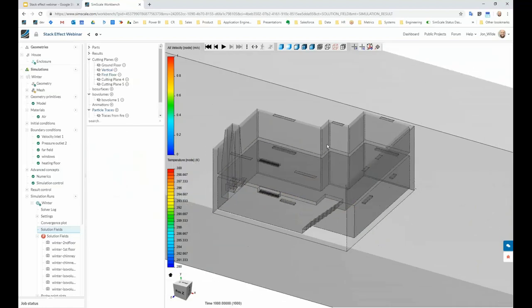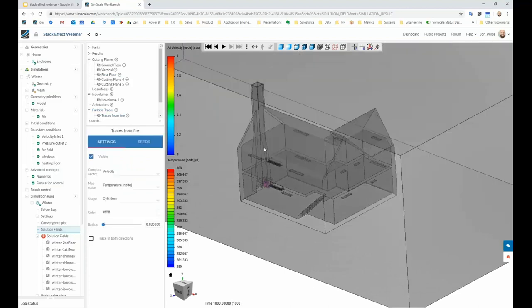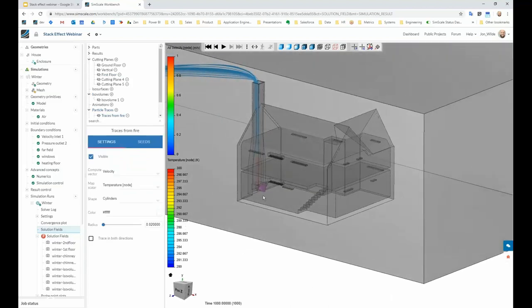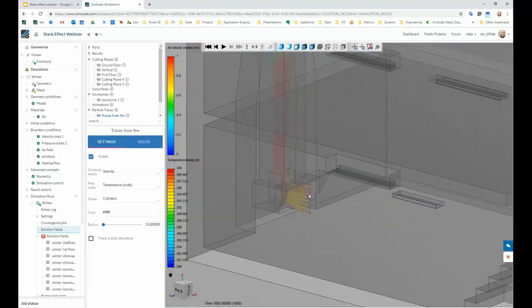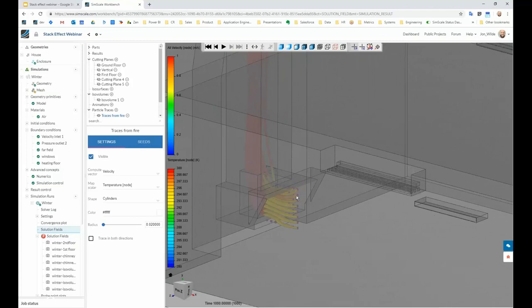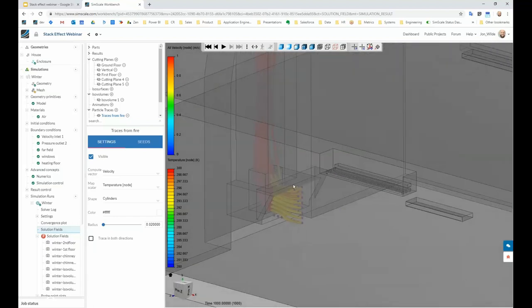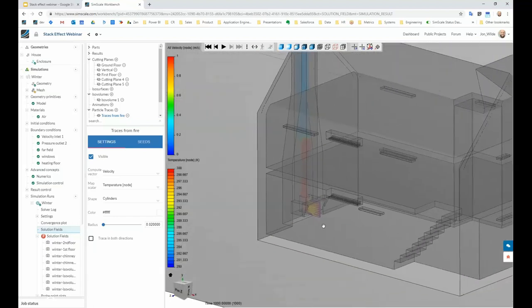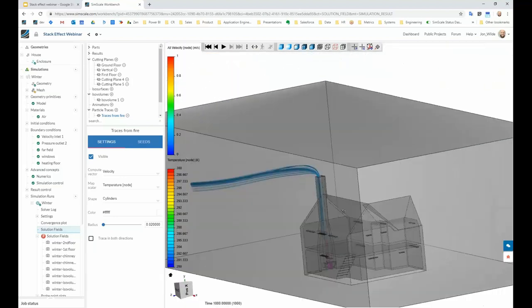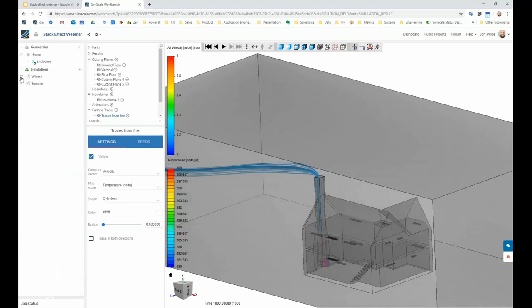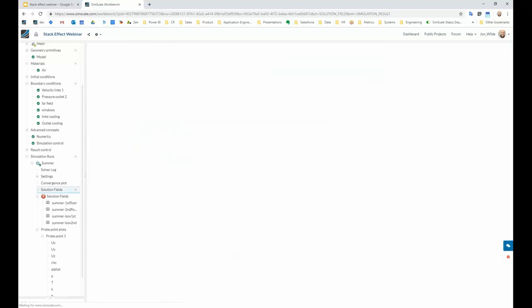We can also look at traces — basically a particle placed somewhere in the model. Here we're positioning it next to the fire. What we want to make sure doesn't happen is that flow comes back into the building, because then the building gets filled with smoke. We just want to be sure everything is leaving. With traces down here, we're pretty confident the flow is exiting upwards, coming out at the roof and then exiting. Now I want to dig into the summer scenario a bit — we'll run through it a little faster and then jump back to the PowerPoint to look at some other results.